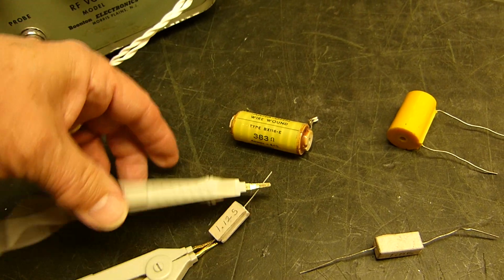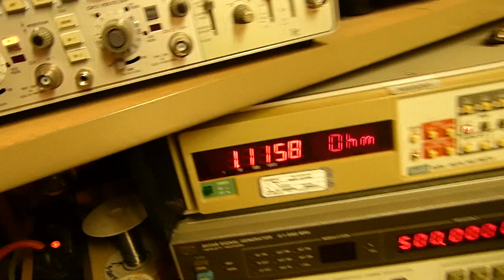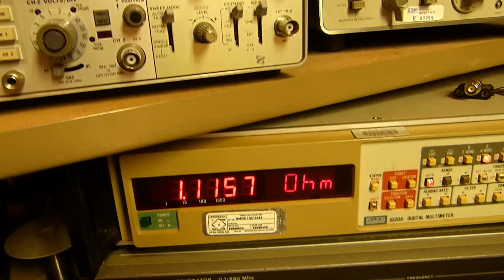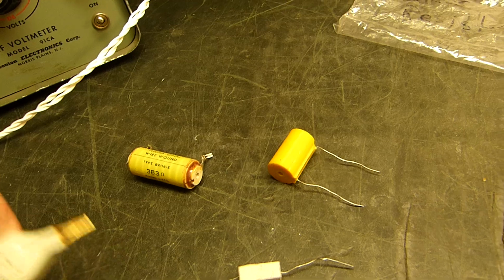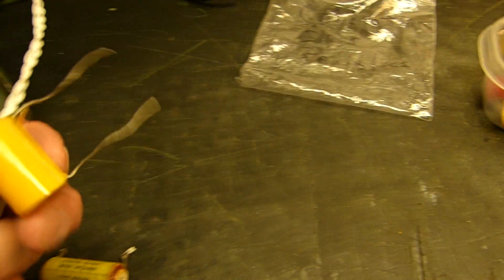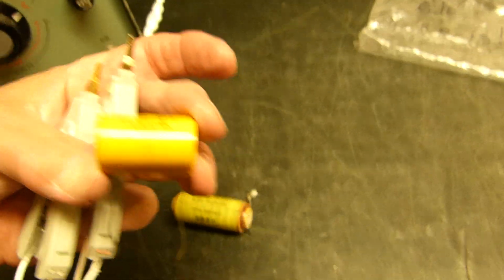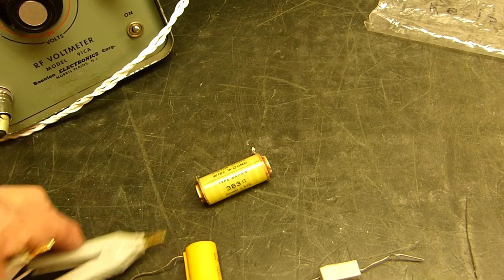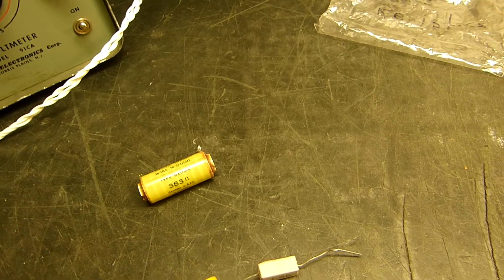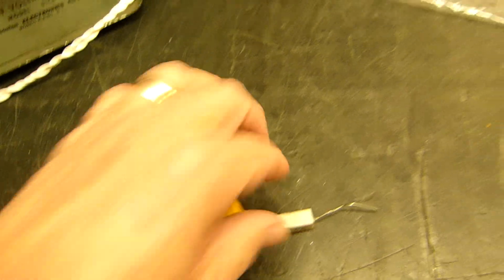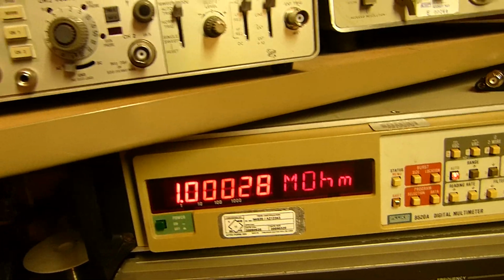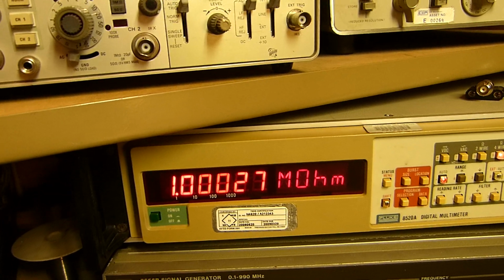Here's 1.125, measures 1.1. You'd round that up to 1.12. And then you can go from there instantly over. Here's what I call my calibration class resistors. I don't know if you can read that. Here is a 1 megohm, 0.1%. And if we clip it across there, that 1 megohm, 0.1% measures 1.00028 megohm. Okay, and here's one right here.